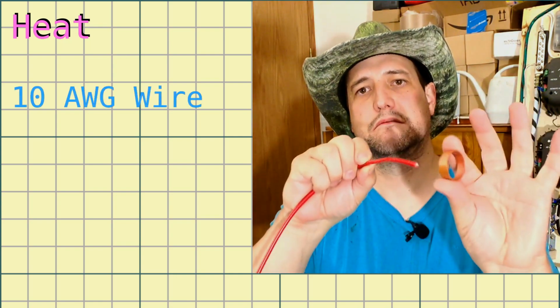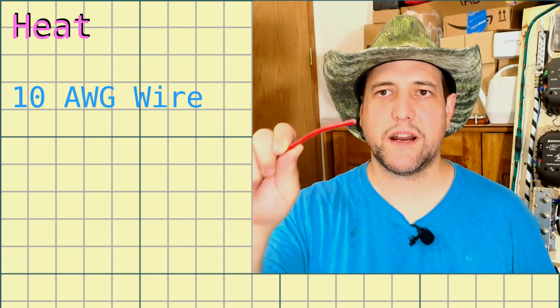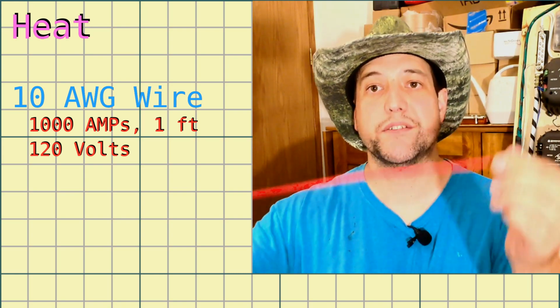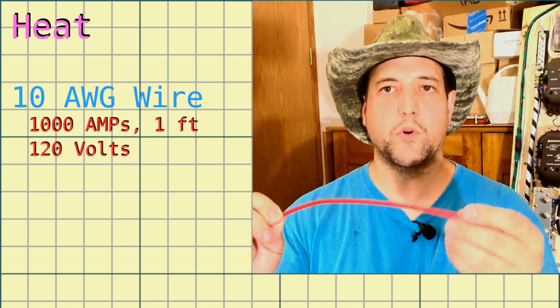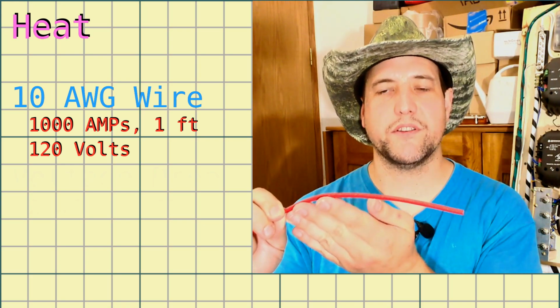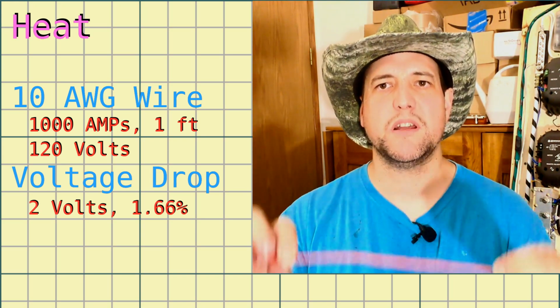Okay, so here's some 10 gauge wire. It's a bit smaller, see? Quite a bit smaller, right? It's a little wire, right? And let's say we want to put 1000 amps down this wire, but we're only going to go a foot. Now, when you calculate this out, 1000 amps over 1 foot of this wire, less than 2% of energy loss. Hey, that's great. We can do this. No problemo. Perfect, right? Everything's good.